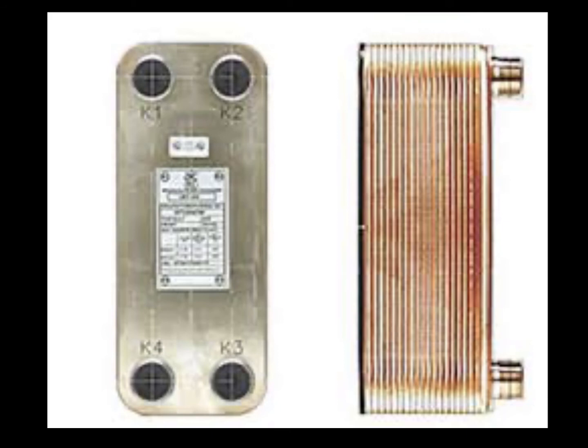When installing this type of heat exchanger, it's important to provide adequate isolation and purge cocks so that a chemical solution can be circulated through the flat plate heat exchanger to remove any scale accumulations that may have occurred over the years.